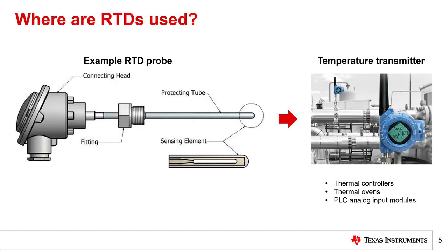Shown on the left is the mechanical housing of a typical RTD probe. The sensing element is inserted into a protecting tube to keep it from getting damaged. This protecting tube is attached to the connecting head, which allows the RTD housing to be held in place such that the sensing element can be inserted into the measurement media, usually a liquid. The sensor wires extend from the bottom of the connecting head to the measurement system. Common measurement systems include temperature transmitters used as part of an industrial control loop, thermal controllers, thermal ovens, and analog input modules for PLC systems.